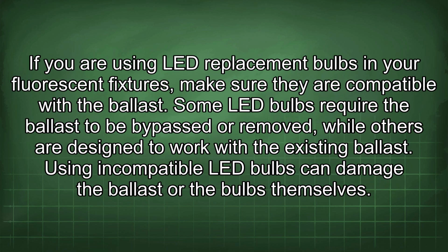If you are using LED replacement bulbs in your fluorescent fixtures, make sure they are compatible with the ballast. Some LED bulbs require the ballast to be bypassed or removed, while others are designed to work with the existing ballast. Using incompatible LED bulbs can damage the ballast or the bulbs themselves.